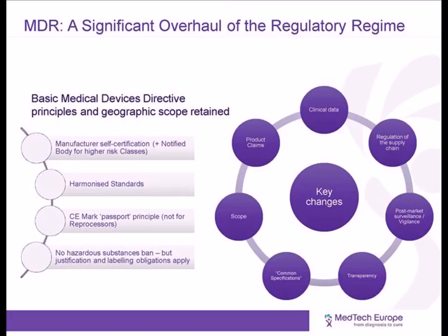And finally, proposals to ban certain hazardous substances were not ultimately incorporated into the new MDR. Nevertheless, if certain devices contain hazardous substances above the specified threshold, this must be justified and labeled. This obligation makes it imperative for companies to know, whether from suppliers, testing, or some other solution, which chemical substances are present in their devices.